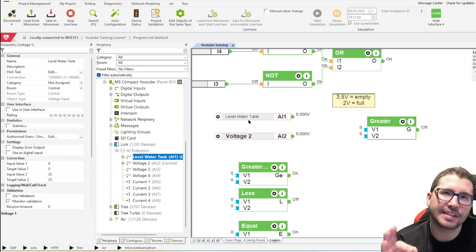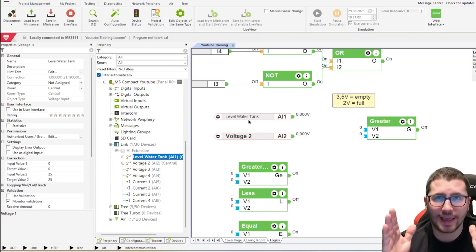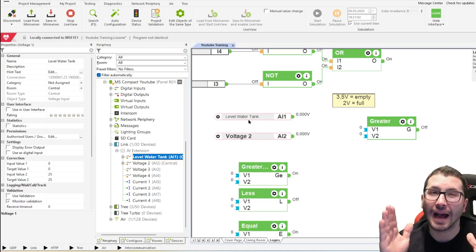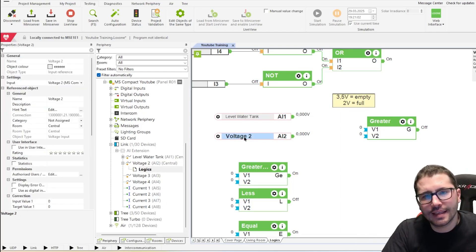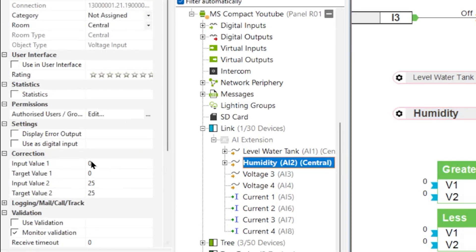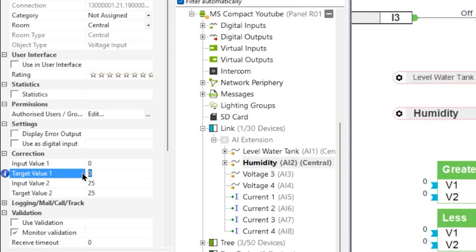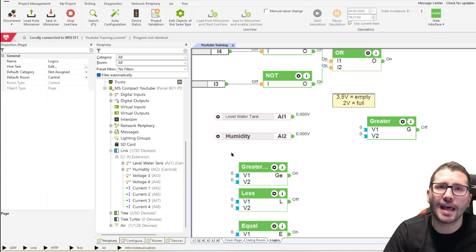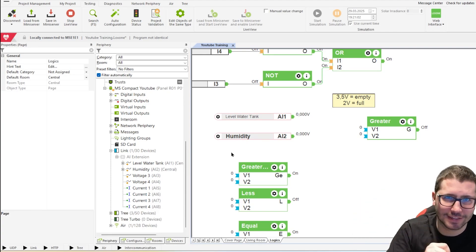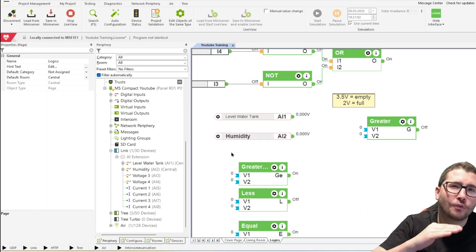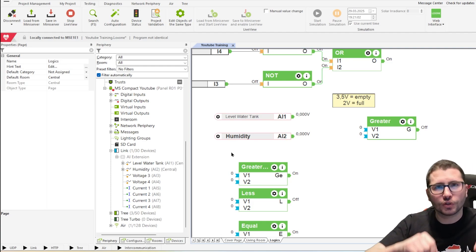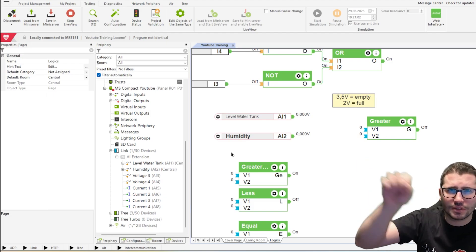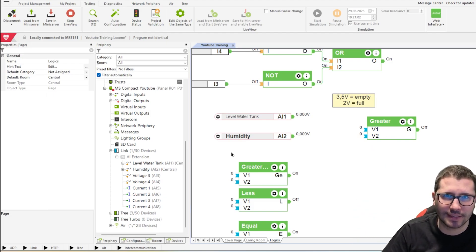As an easier example, let's say we have a 0 to 10 volt sensor delivering 0 to 100% humidity. In this case, we would say the input value 0 volt means 0% humidity. The input value 2, 10 volt means 100% humidity. And everything in between, that's why I make this example, 5.5 volt means 55% humidity. So Loxone is doing a linear, what's the English word? A linear interpolation, like in school, the freaking linear graphs things. Now you know what you needed this for.